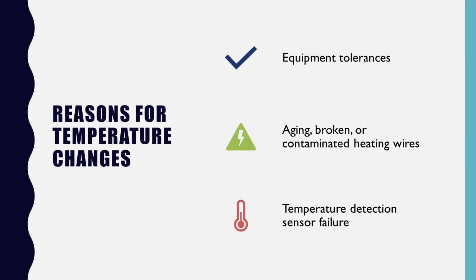There are temperature-sensitive blocks in the sintering machine, so it's important to follow the manufacturer's recommended temperature. There is a slight difference between the temperature displayed by the machine and the actual temperature. If the heating wire becomes thinner or dirty with use, the temperature can drop, or it could overheat if the temperature sensor is broken. For these reasons, it's necessary to check the actual temperature.